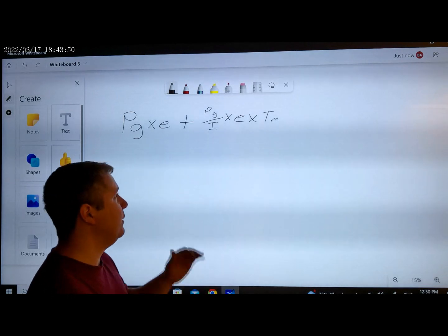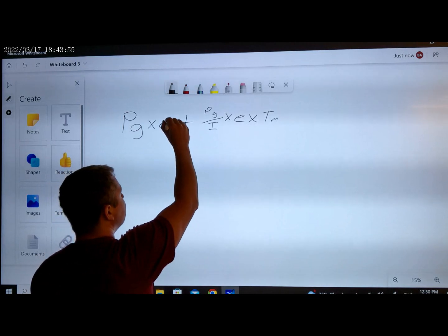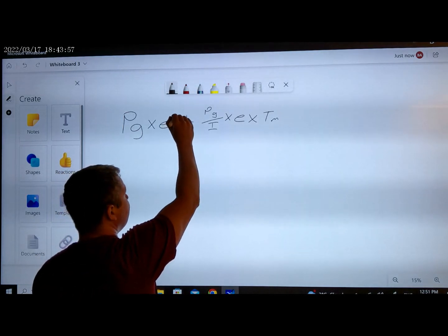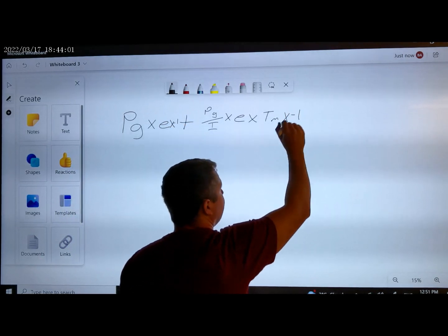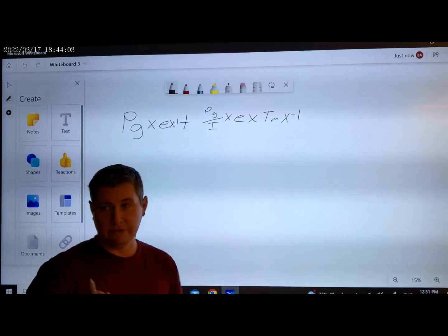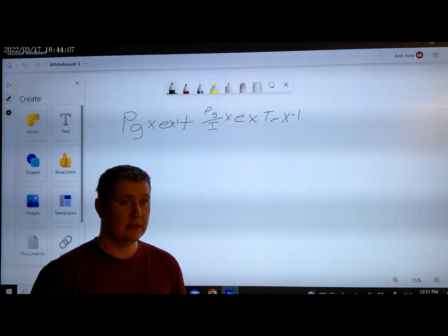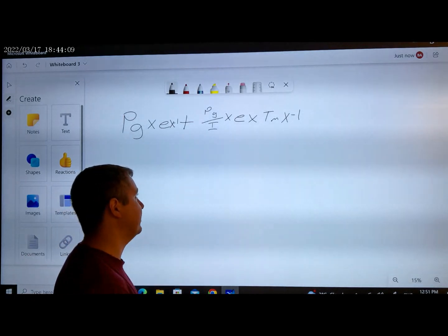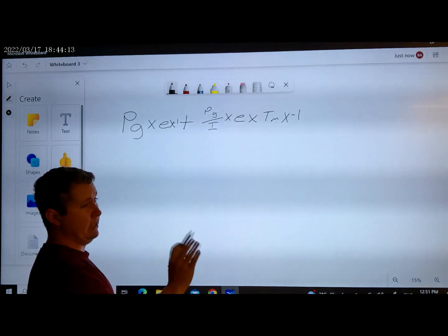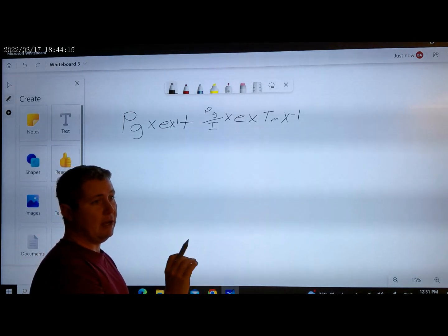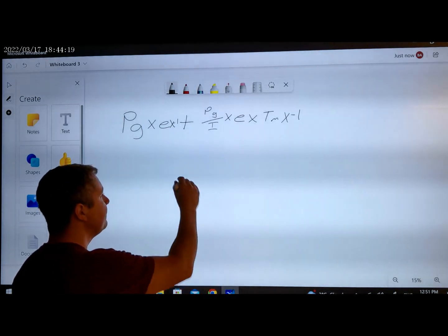When we have reverse acting, we're always going to have times minus 1, and that puts all of our outputs reverse acting. Keep in mind we haven't got the derivative yet. So now, whatever the error is, our output is going to be the opposite.